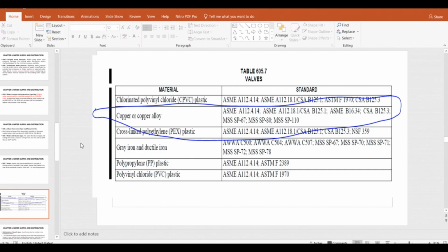So what is so important in the plumbing system? For example, some accessories will come from Europe, some pipes will come from other parts. If coming from Europe, they will follow the British standard to make the valve. The piping which is coming from other parts might sometimes follow the American standard to make the threading for the flanges. So we have to make sure that both are compatible to make the connection.